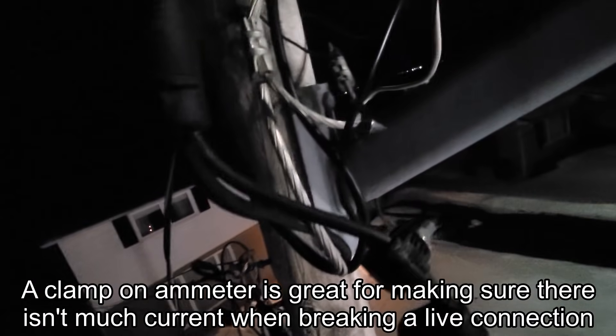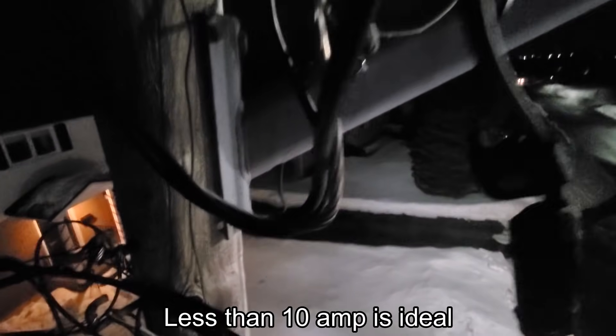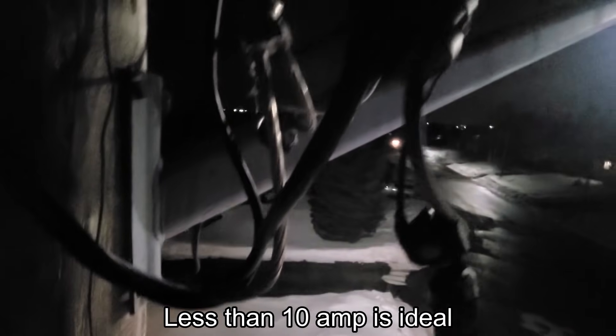We're up in the air here — that's all live, 120/240 volts — and I'm going to be cutting this while it's energized, which is no problem. I do need to watch that neutral. Whoever hooked this up left the triplex all wound together, which is not really good practice. I'm probably going to want to cut it right around here so we can keep that street light on. The wires are spread out a little more, which makes it a little easier and safer to work with.